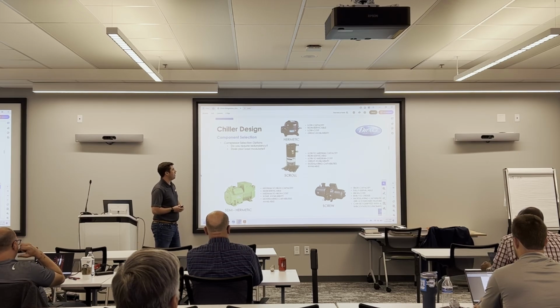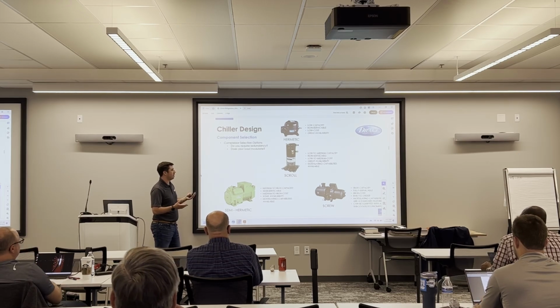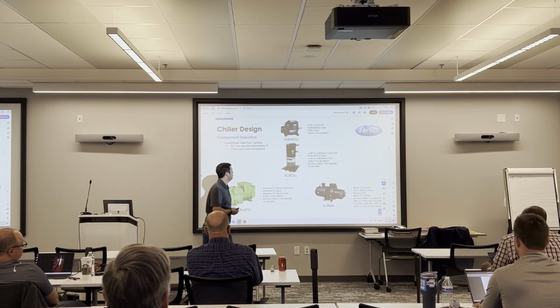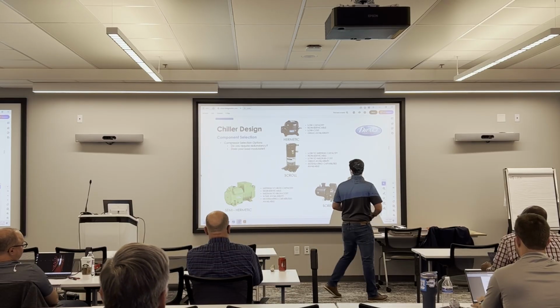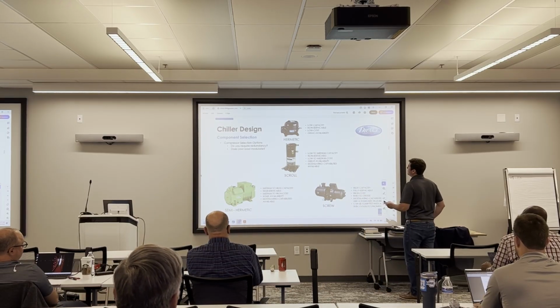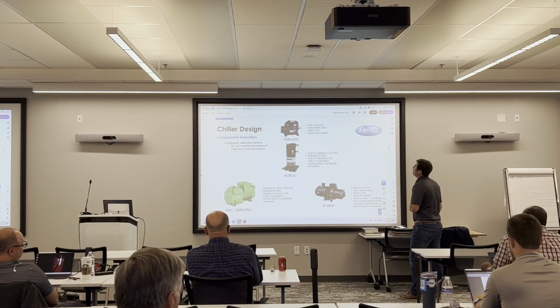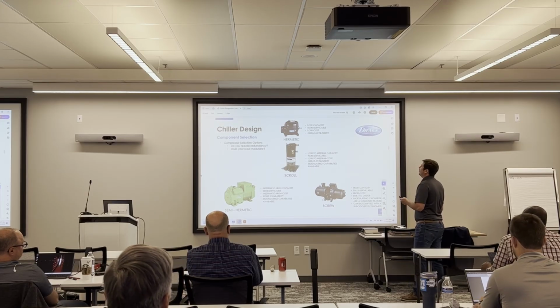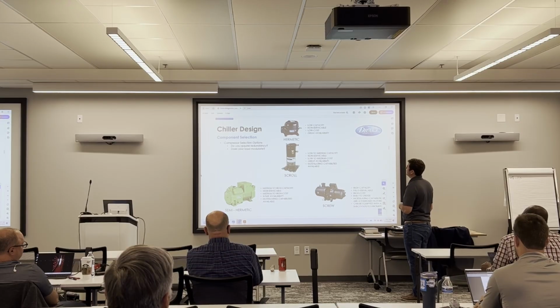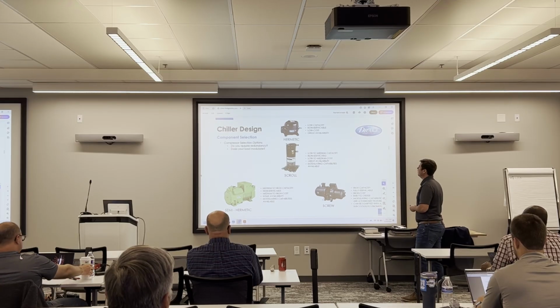All right, so we've got a couple different compressors on here. These are all compressors that we use at Drake. I'll go through each one. The first one on the top is just a small hermetic compressor. You see this on a lot of refrigerators at home. So hermetic is generally used for low capacity, low tonnage units. It's not serviceable; the whole compressor is hermetically sealed, so you can't get access to the motor or anything like that.